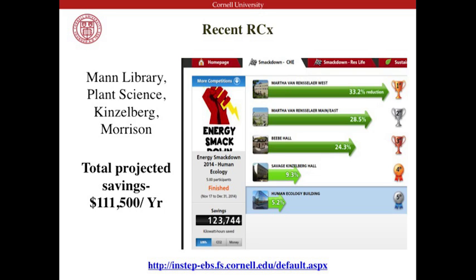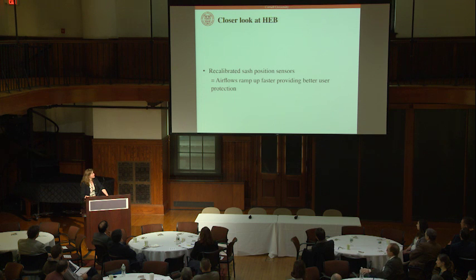We ended up recalibrating the sash position sensors. They weren't commissioned correctly initially, and weren't set up right. The airflows are now ramping up faster, providing better user protection. Before, when somebody opened the sash, it was taking a long time for the airflow to increase. That's a safety value.